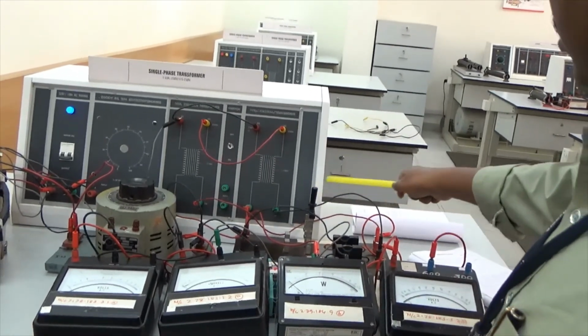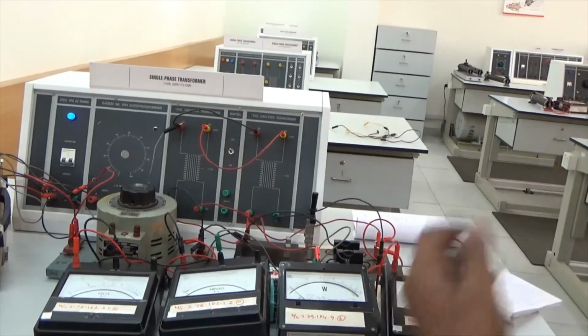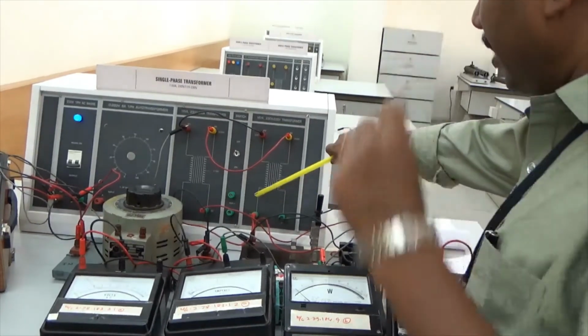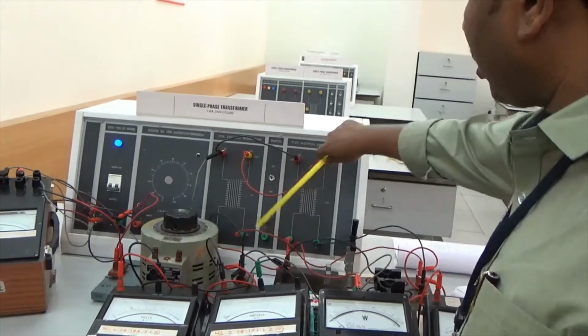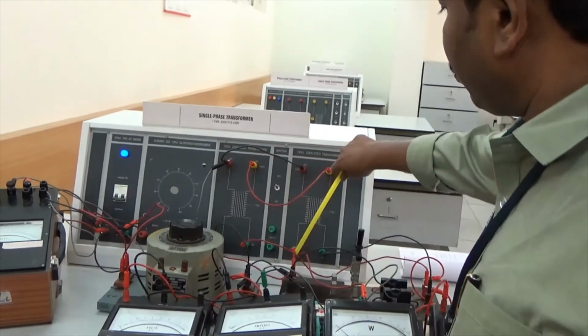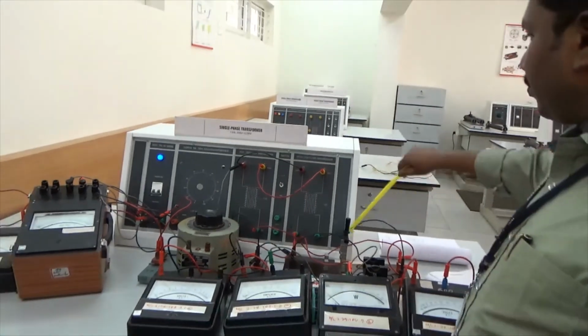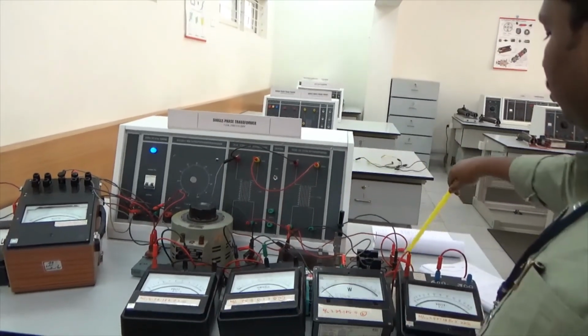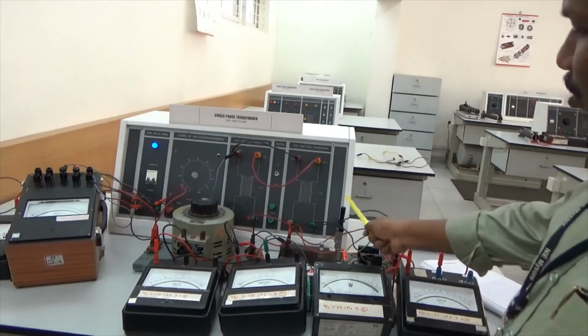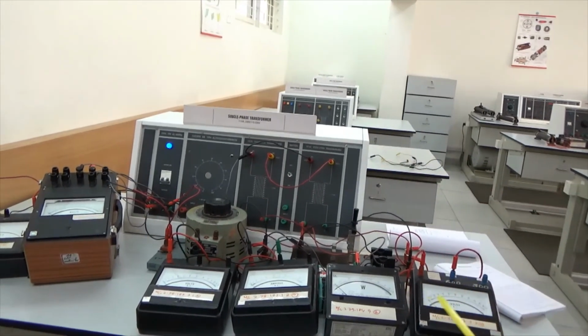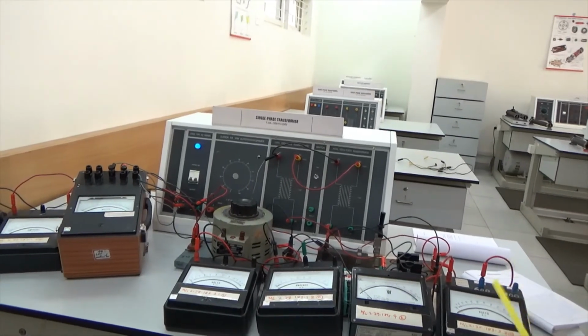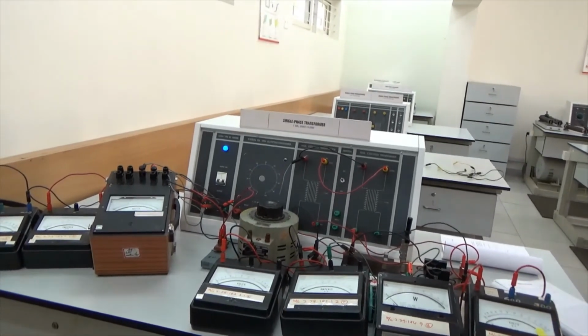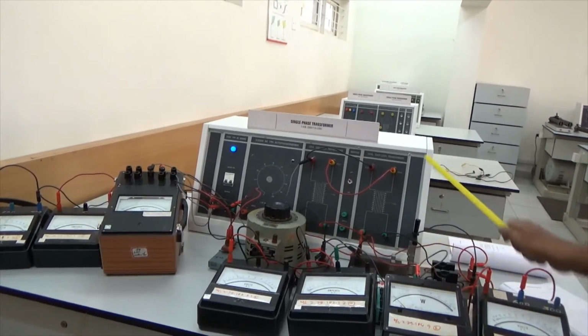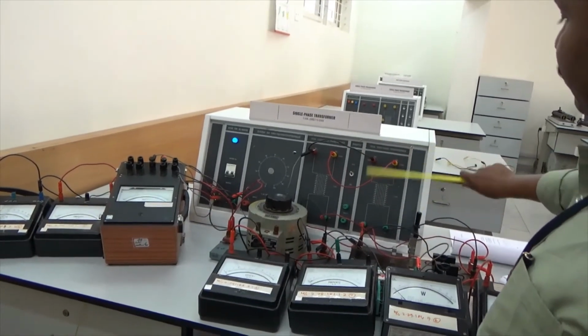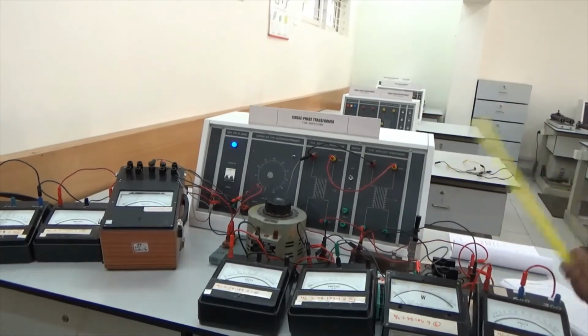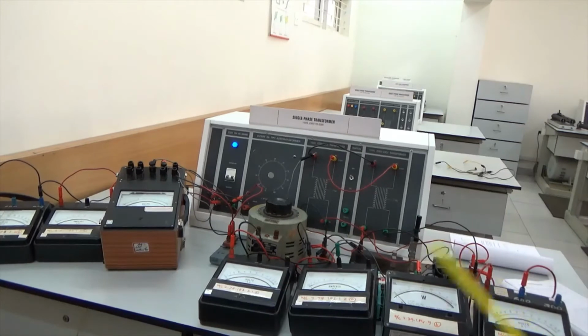Interesting is that there is one more switch, a DPST switch, the double pole single throw switch. The primaries of the two are connected in parallel, and the secondaries of the transformers are connected to one side of the switch. Before closing the switch, you have to ensure that the voltage across the two series connected secondaries should read 0. That is only 0 if the secondary voltages of the two transformers are in phase with each other.